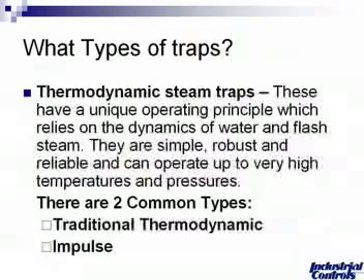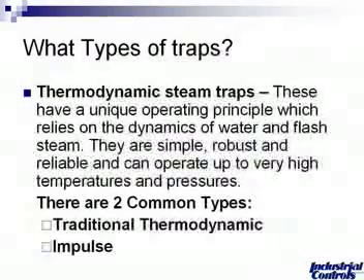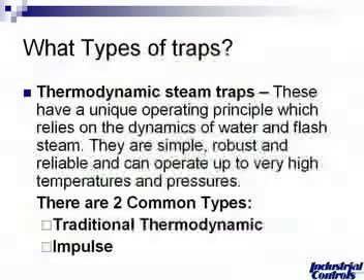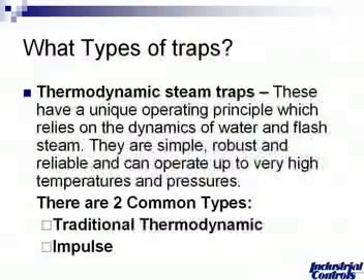Another family of traps is the thermodynamic steam trap. These have a unique operating principle which relies on the thermodynamics of water and flash steam. They're simple, robust, very reliable, and can operate up to very high temperature and high pressure. There are two common types: a traditional thermodynamic or disk trap and the impulse style trap.